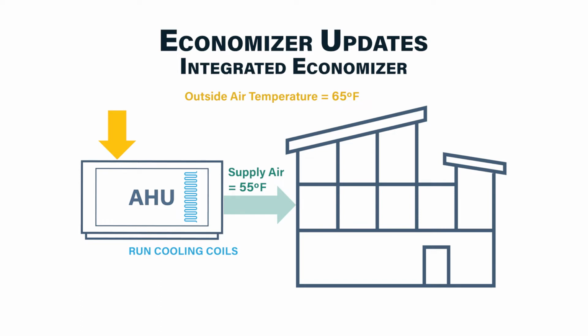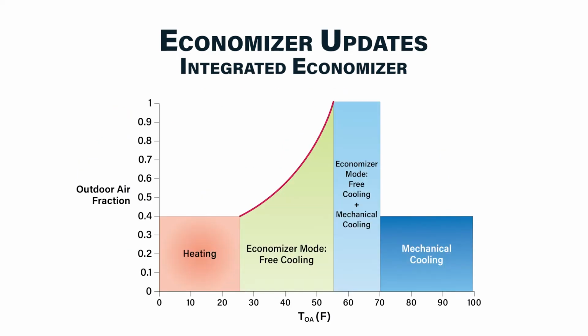This is called integrated economizer, where we're running the cooling coils with 100% outside air until it's cooler or less humid inside than outside. Here's an example of the control sequence for an economizer with integrated economizer mode. During our heating mode, we're running at minimum outside air. As it starts to warm up, we enter our free cooling mode where the outside air damper begins to open. Eventually we'll hit 100% outside air, and then we'll run an integrated economizer mode where we're at 100% outside air and we're running our mechanical cooling. And then we'll hit a certain high limit temperature where we close the outside air damper, we go to minimum outside air, and we're in mechanical cooling only.